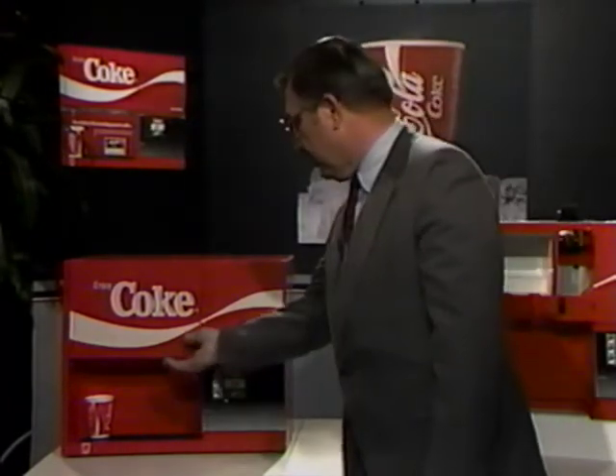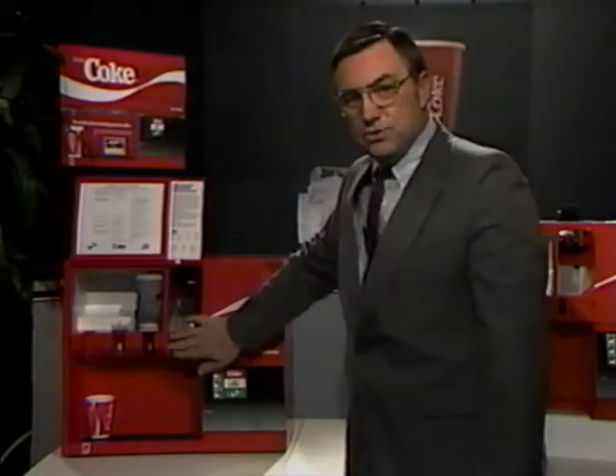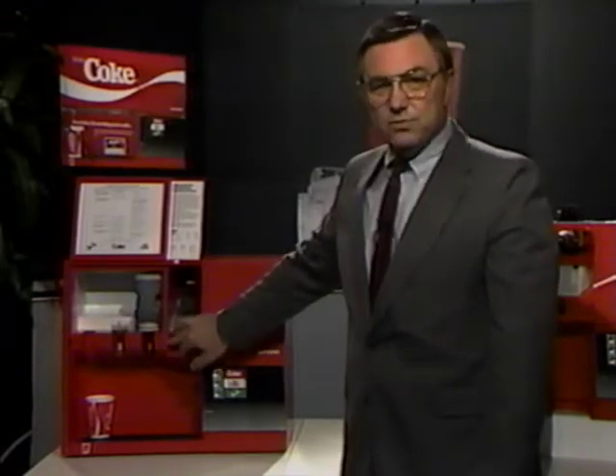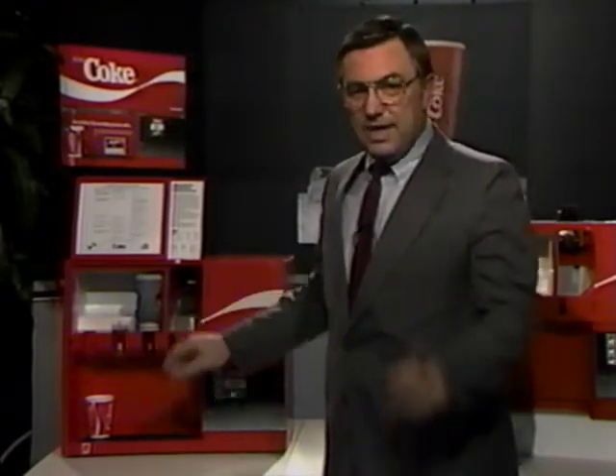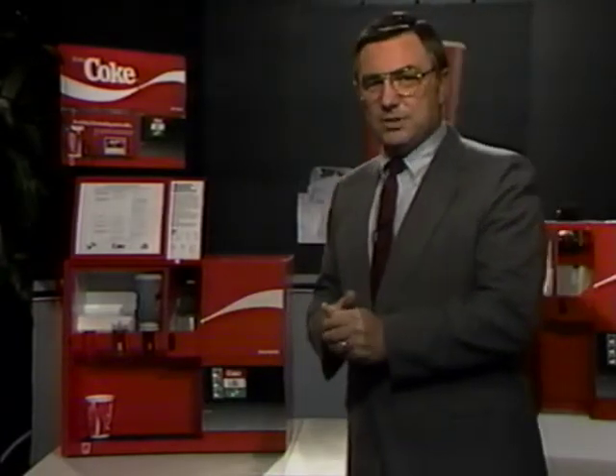So when you see a blinking green light, the A light, first of all, you want to turn the machine off. This resets the timing cycles. The next thing you want to do is turn your attention to the water supply. If it's been shut off for some reason, then look for the reason. Look for valves not fully turned on, for pinch lines, look for a filter being clogged, or even see if there's low pressure in the building. And the easy way to check is to just disconnect the machine at the back and check for a 4 quarts a minute flow rate. Then you know you've got enough water to run the machine.